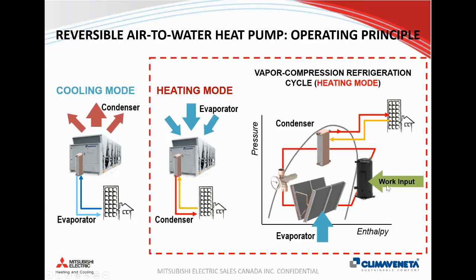So here on the right is just showing the refrigeration cycle. So again, you see the coil on the machine, the evaporator. We're extracting heat, and by using a compressor and inputting work into the system, we're moving heat from one location to another, supplying hot water to our building. In order for us to move heat from one location to another, and specifically in order to extract heat from the ambient surroundings, we need to send refrigerant to the evaporator that's at a colder temperature than what the ambient conditions are. So typically with air-to-water heat pumps, it's the refrigeration itself that will limit the ambient temperatures that you can run the machine down to.